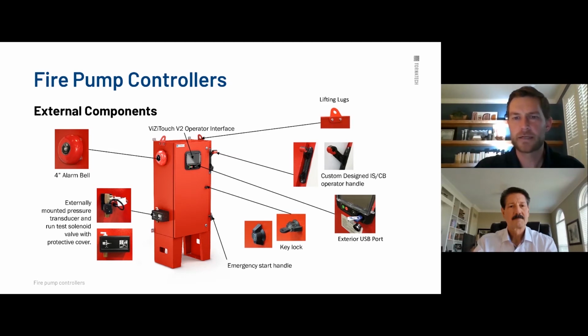Another thing, I don't know if there's another slide that shows a close-up of this, but over here, I know Marty had mentioned the way that you can get the saved logs and everything that's inside the ViZiTouch. We have an exterior USB port, so you don't have to open up the control panel to get any of the data off of it. You can just plug your USB into the bottom right of the ViZiTouch and go through the download process and get all the data that the controller has been recording ever since it's been powered up. So it'll be your power, your amperage, your pressure, your every start and stop. We keep track of everything, so you can get that data off of that USB port.